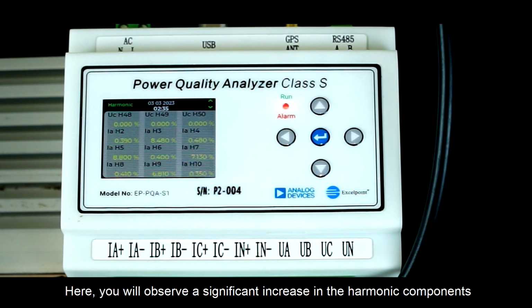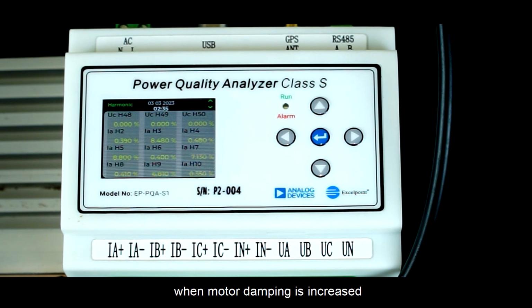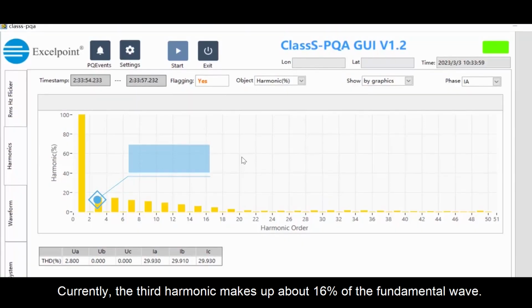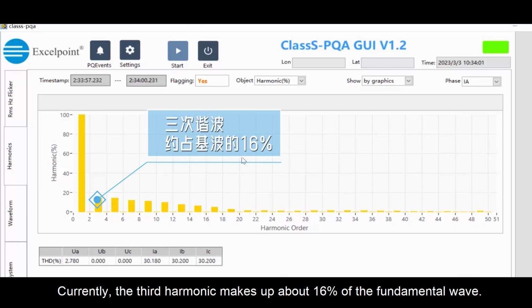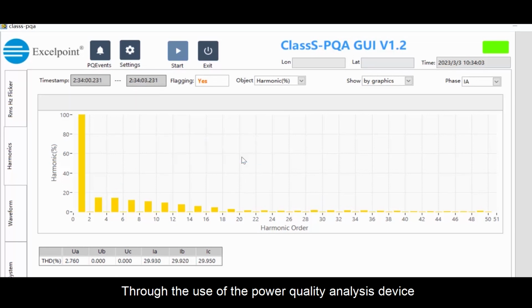Here, you will observe a significant increase in the harmonic components when motor damping is increased. Currently, the third harmonic makes up about 16% of the fundamental wave. Through the use of the power quality analysis device, we are able to observe the variations in the alternating current (AC) motor harmonics under 2 different damping conditions.